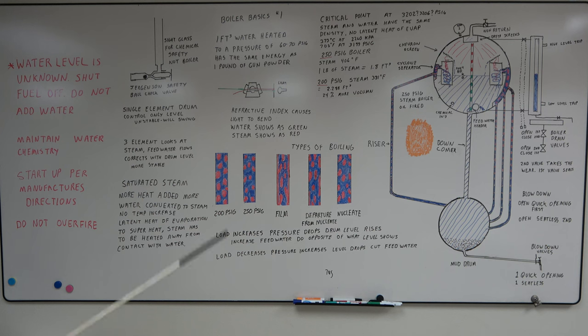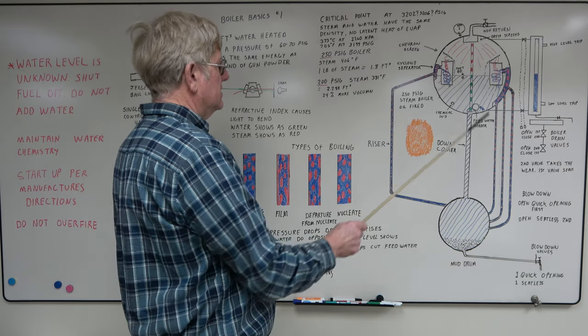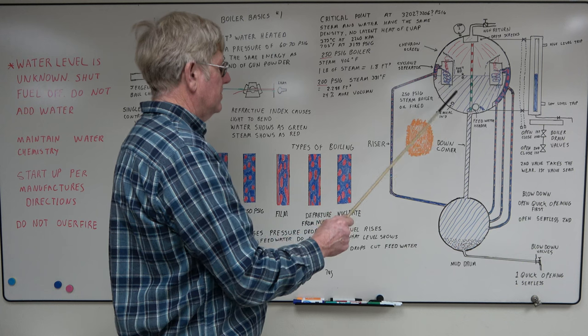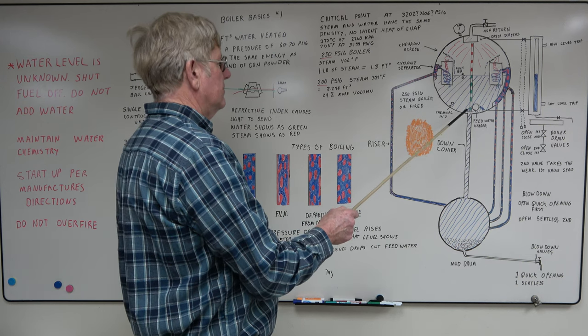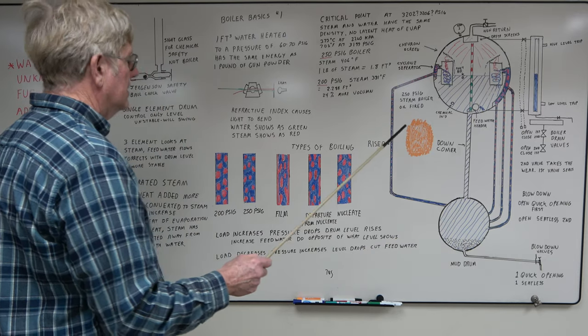Okay, the most important part of this whole thing, the one thing that everybody really, really needs to understand. If water level is unknown, shut fuel off. Do not add water. This has killed more people than about anything with boilers. So if you walk up to a boiler, this is all red, you don't know what the sight glass is, you just walked up to it, trip it, shut the fuel off. Add water to this thing could cause an explosion.